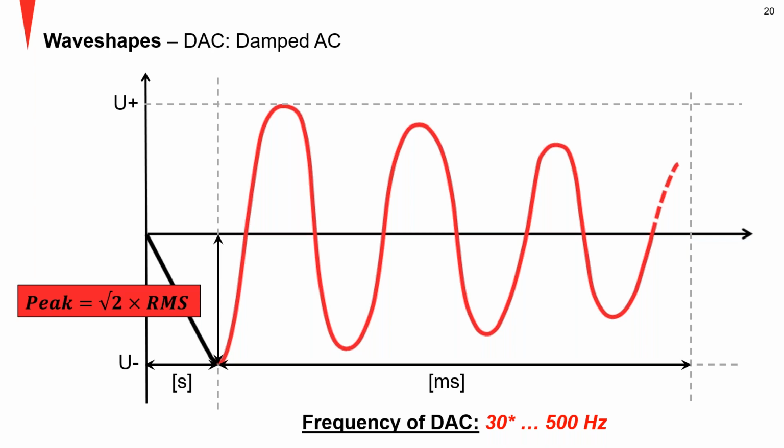There is a defined frequency band for that, which is the so-called IEC frequency range. That frequency range was established for the resonance test sets, the big resonance trucks in the, let's say, 1990s. And the damped AC waveform was the first that was qualified and investigated and found to be completely comparable to line frequency.